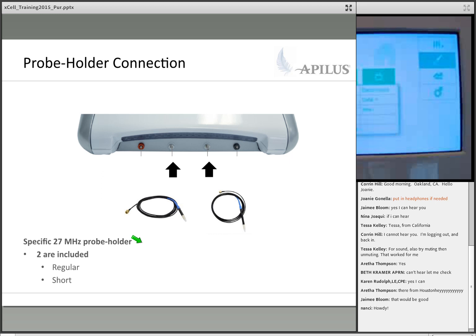The probe holders get plugged into the front. The probe holders are going to be specific to the 27 megahertz machines. This is why they're actually different as far as the plug part from the 13.56 megahertz machine. So if you've had one of those in the past, you'll notice that you cannot interchangeably use the cords from one to the other. They get screwed into the front there. And the machine comes with two different types of probe holders when you buy them. One is called the regular, one is called the short.